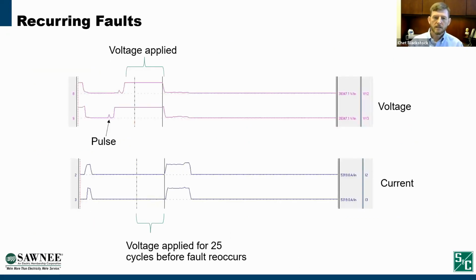So this is an example from the oscillography from our system in one of these events. The top oscillography chart represents two phases, poles 1 and 2, and it's the voltage on those two phases. You can see the small bump in voltage where the pulse occurs. That's the low energy pulse that Mike described. It did not detect a fault, so you see the voltage increasing and going up to system voltage for some time before it goes away again when the interrupter trips again.